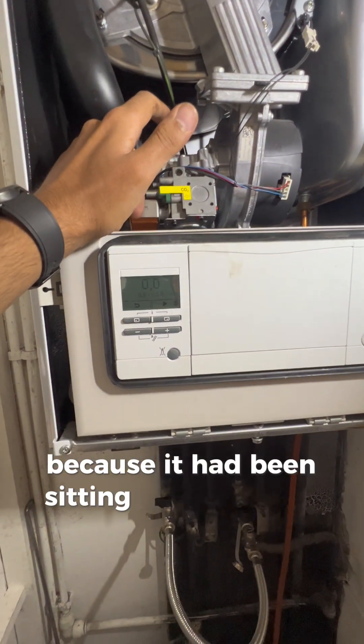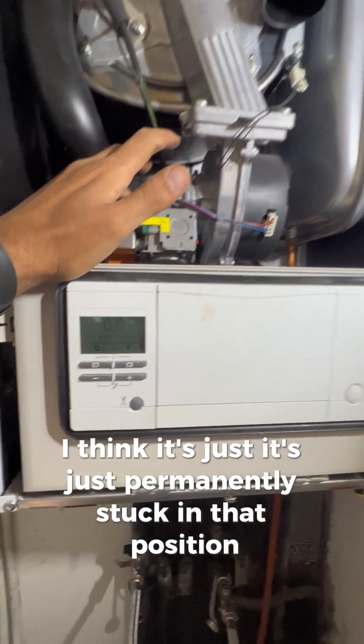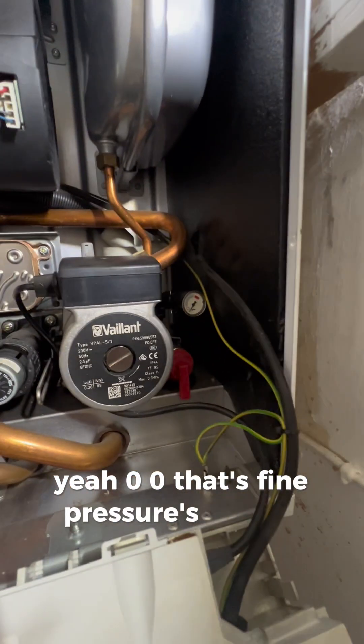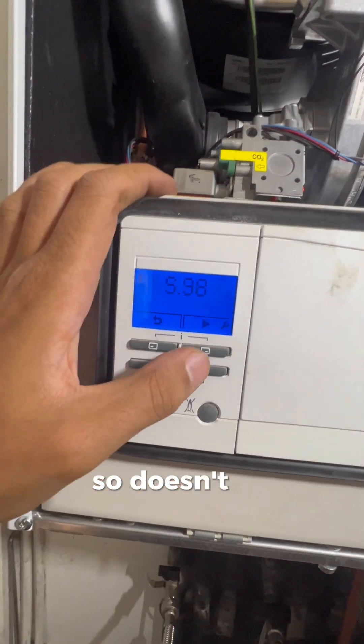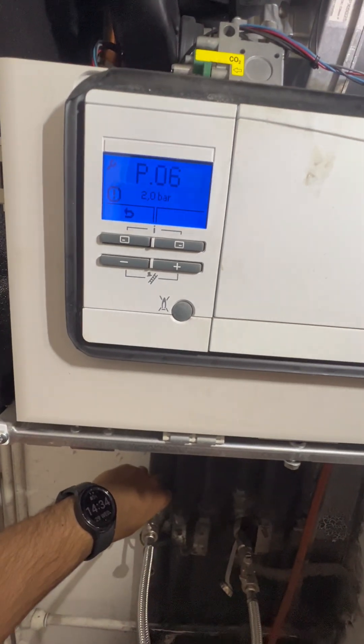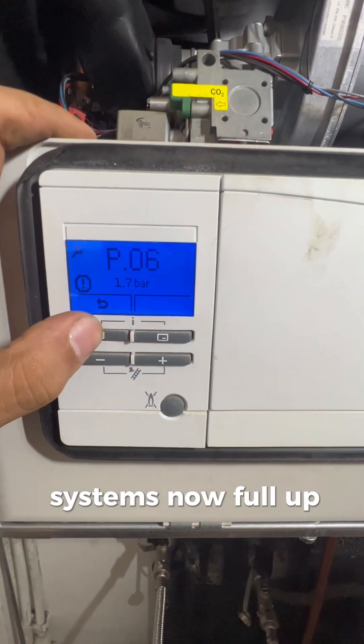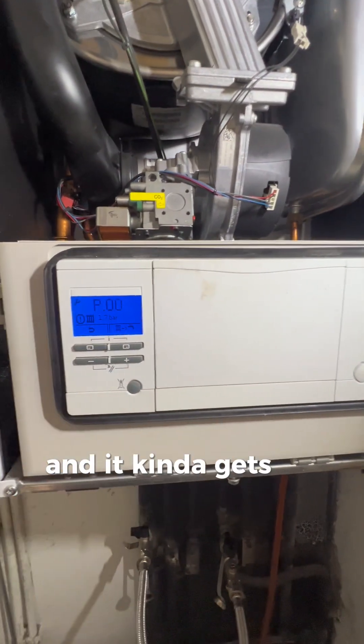I've had to change that sensor at the back. I think what happened is because it had been sitting at three bar for maybe a year or two - the customer said he's had this issue - it's just permanently stuck in that position now. Even after cleaning it, it was the same thing. But now you can see the new one's in - zero. Pressure's on zero. I've put it into filling mode now. Let the system fill up. System has filled up. Putting it into purging mode - it pushes the pump one way, then the other, and gets rid of all the air in the system.